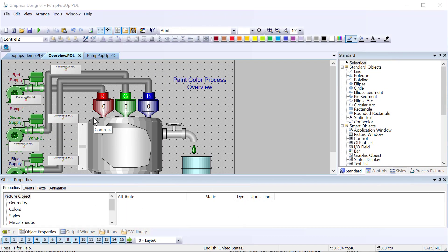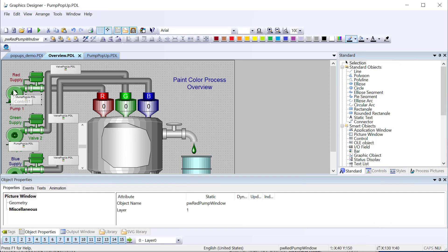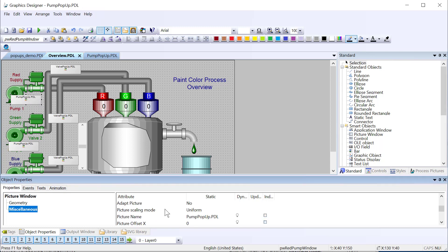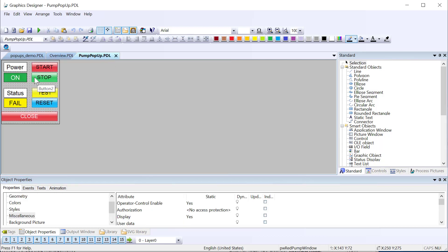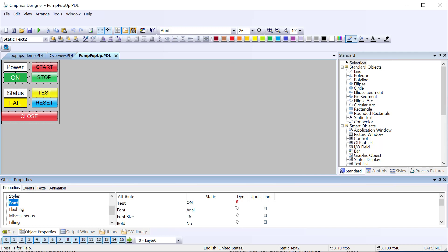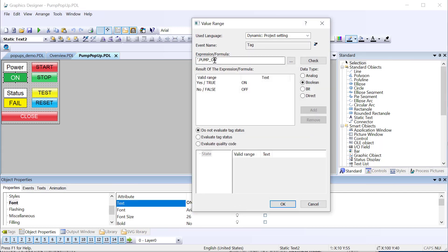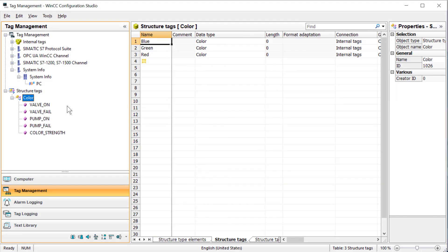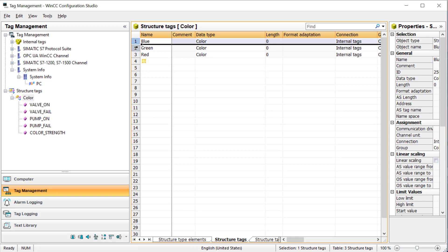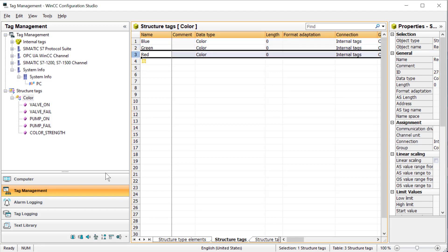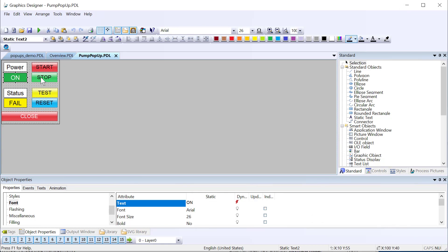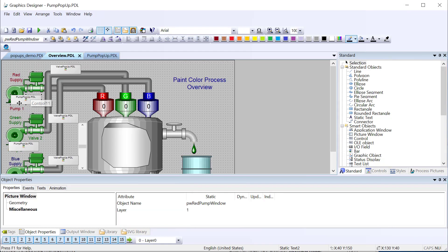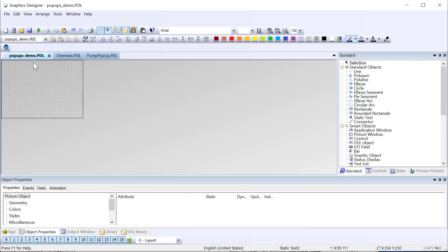So we're going to start in graphics designer. On our overview screen currently, we are using picture windows. When you click the pump, it just shows this picture window showing this pump pop-up PDL. If we take a look at the dynamics, you can see that we're using a tag prefix for this page. Looking at tag management, I do have a structure tag, which has my valve on, valve fail, pump on, pump fail. If we go look at the tags, you can see I have a blue, green, and red series of these structure tags. That's what I use to populate this pop-up depending on what pump you click. So what we want to do is get away from using the picture window and just use a script to show it. That way we don't have all these picture windows.